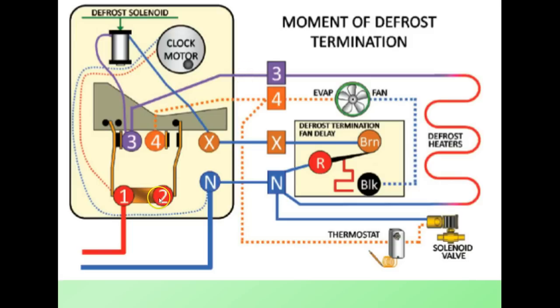At the defrost termination, the evap fan is off and we still have 115 volts to the defrost heaters.